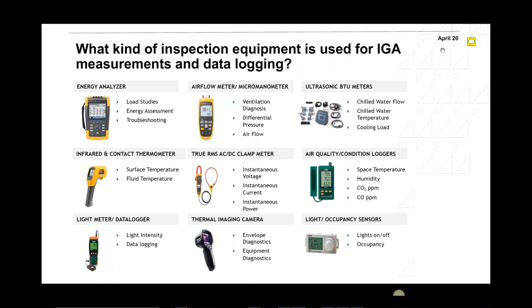Indoor air quality: CO2, VOC, CO, especially if I'm doing any car park measurements to see if the car park is well ventilated, and if I can reduce the speed of the fans to gain some efficiency while still making sure the CO levels are within the requirements. Light meter, thermal imaging camera: I can use that for envelope diagnostics if I want to check whether there's proper insulation or not.